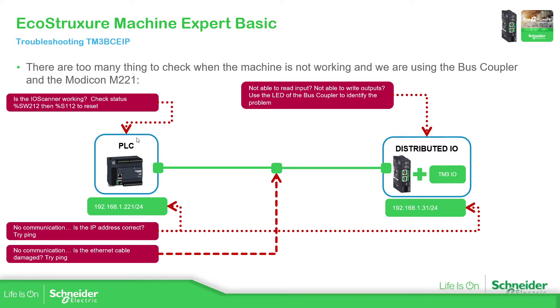If we start with the PLC, we need to check if the IO scanner is working. I have already made some videos on how to check the IO scanner communication. Here are the two parameters. We need to check the status — this lets you read the actual status of the IO scanner to see if it's working or not — and then this one is to reset.